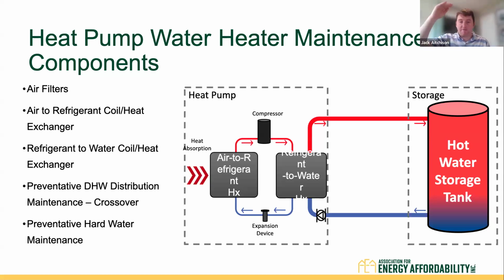Heat pump water heaters start at such high efficiency. As they start to degrade in efficiency, you're going to see that in your utility bills. So it's really important, if you have a heat pump water heater, to be considerate of crossover and replace those shower cartridges, avoiding crossover issues that are going to increase your utility costs. And then hard water maintenance as well. This is really dependent on the location of your property, but in terms of the pecking order of water heating equipment that is impacted by hard water, you have your tankless water heaters, which are the most impacted. Then you have your heat pumps. Then you have your standard gas water heaters and boilers that are less impacted. The reason for that is heat pump water heaters have really small flow paths through that refrigerant to water heat exchanger, so they're easily clogged through scaling from hard water.